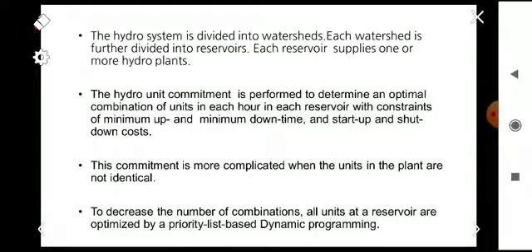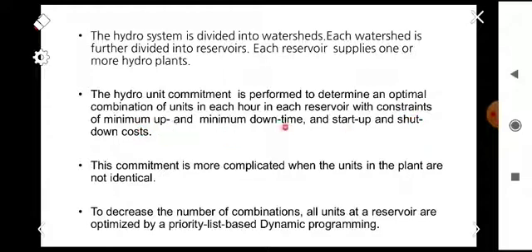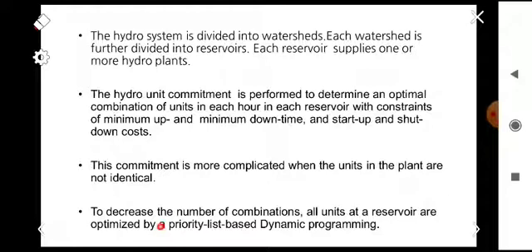The next constraint is the hydro constraint. The hydro system is divided into watersheds, and each watershed is further divided into reservoirs. Each reservoir supplies one or more hydro plants. The hydro unit commitment is performed to determine an optimal combination of units in each hour for each reservoir, with constraints of minimum uptime, minimum downtime, and startup and shutdown cost. This commitment is more complicated when units in plants are not identical. To decrease the number of combinations, all units in a reservoir are optimized by a priority list-based dynamic program, which is a method of solving the unit commitment problem.